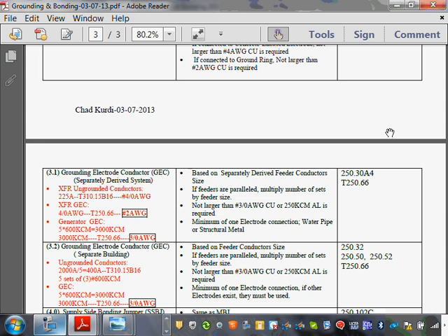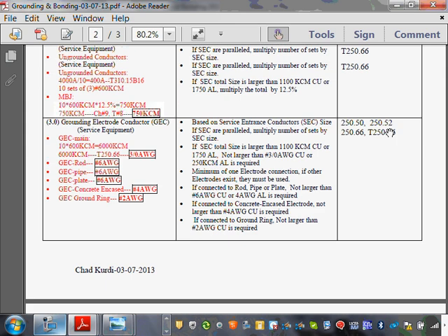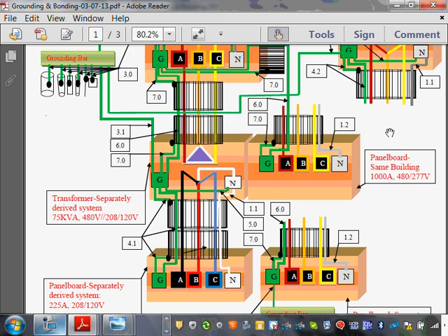Any comments, guys? Any questions about sizing the grounding electrode conductor for the generator? That 3/0 AWG could be tied to a grounding rod next to the equipment, or it could be taken all the way back. If your generator is indoor, what they do is take the grounding 3/0 AWG all the way and tie it to the ground bar, like I did here. Typically, this is for indoor generators. You can see I'm taking my 3/0 AWG all the way back to the ground bar, which is tied to all the grounding electrode system inside my building.